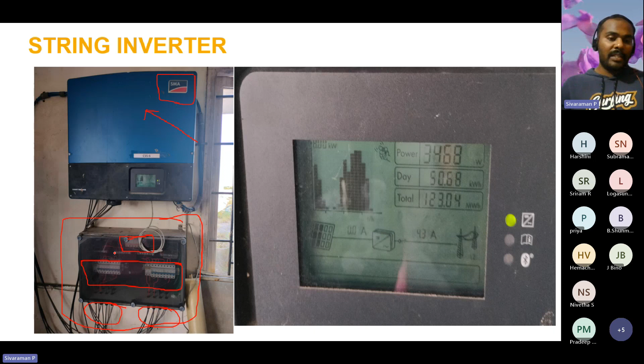So from the solar panel, the positive and negative termination will come here. These are all the positive and negative cable terminations. So if the cable is coming as an input, it will go as the output to the inverter. Inside that, the MPPT will be there, so depending on how many MPPT there are for this inverter, we have to connect accordingly.